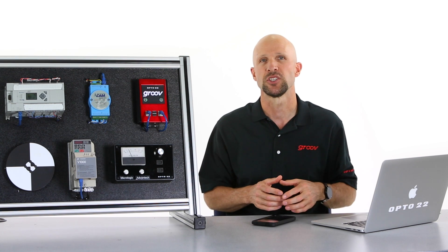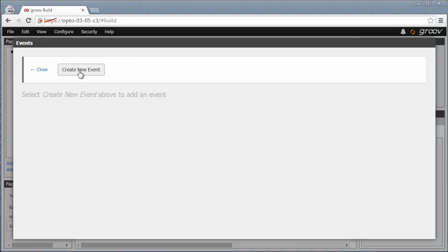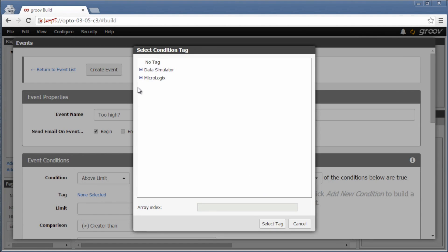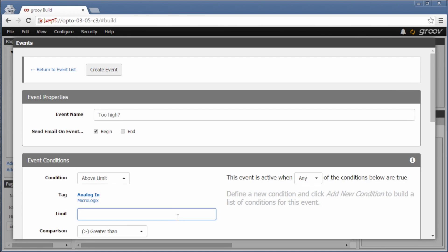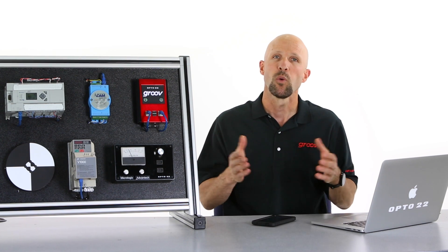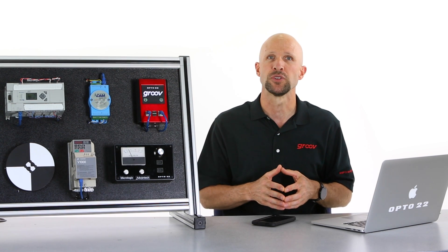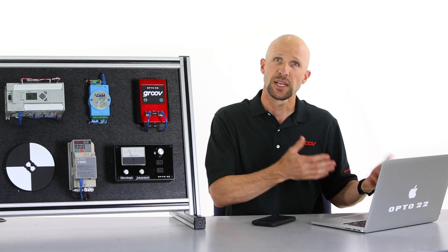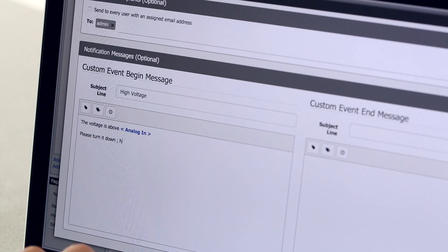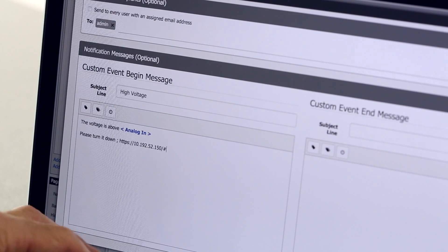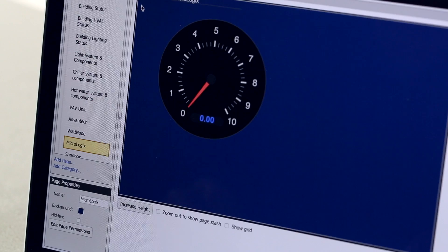Now we're going to add an event message to the tag. Click new event, give it a name, the condition — it's going to be above the limit — then select the tag which is linked to our analog input, and we'll trigger the event when the value goes above 10. Now who gets this email? Well, any authorised groov user can be added to this notification, but for now that's just going to be me. Let's add some custom text to this email, and here's where we can include a link to the groov page. Done, done, and done.